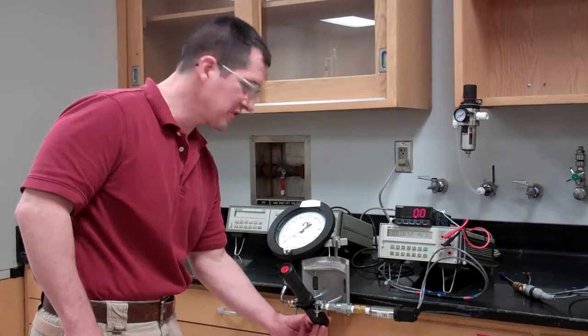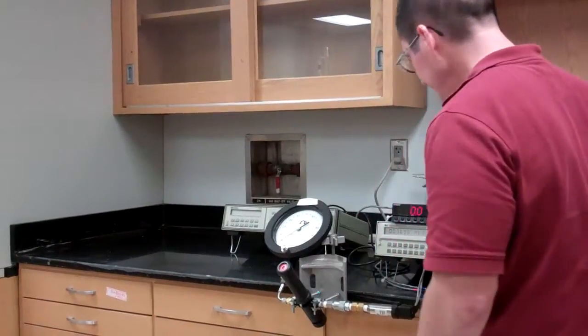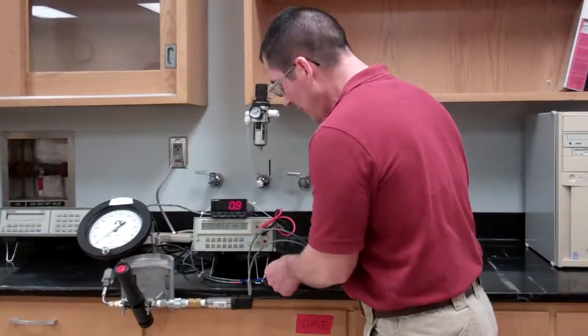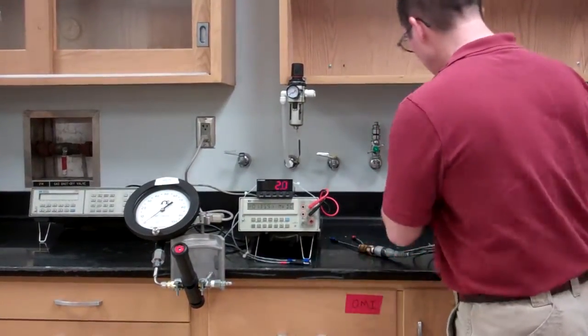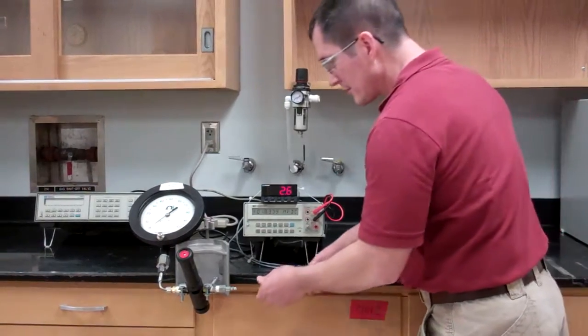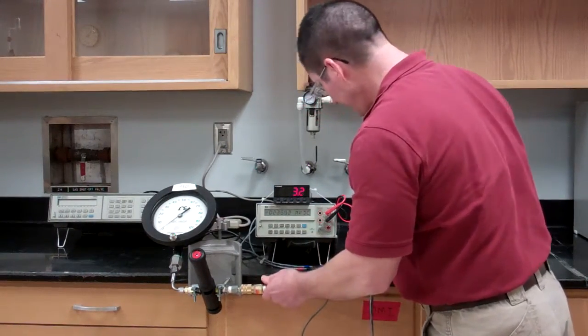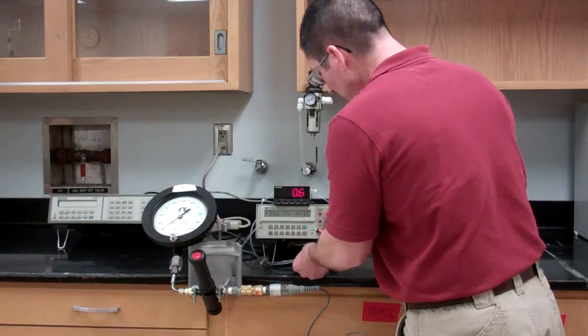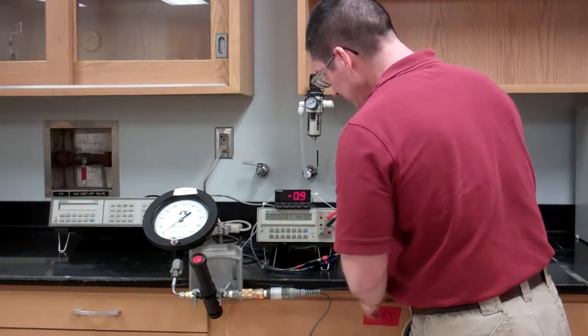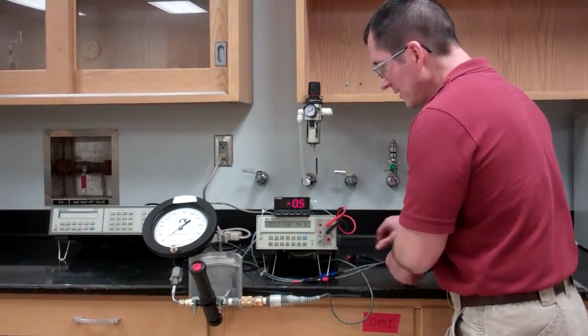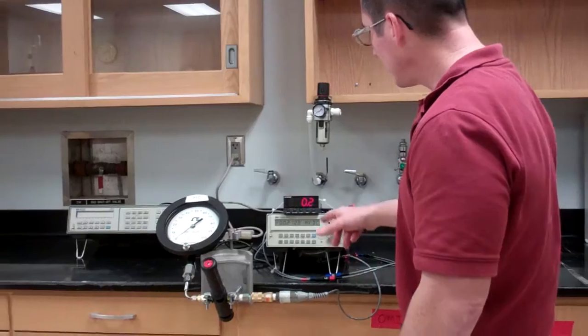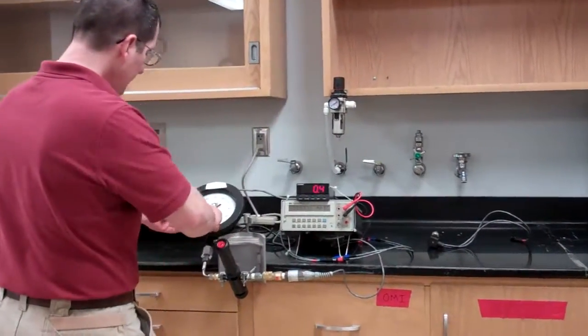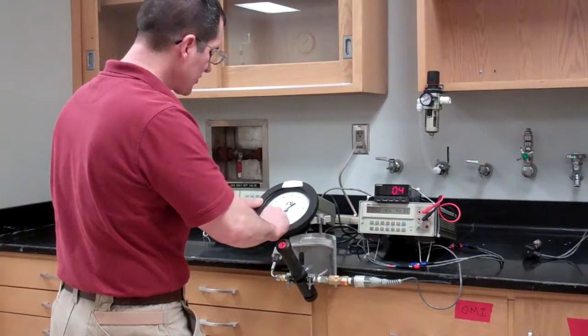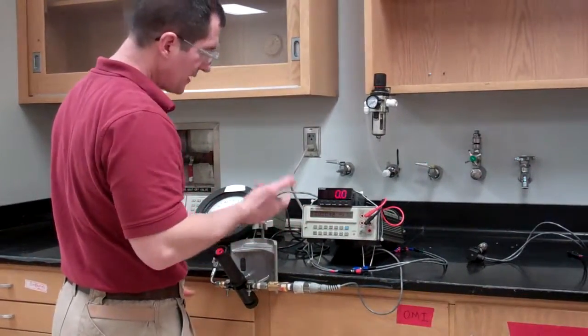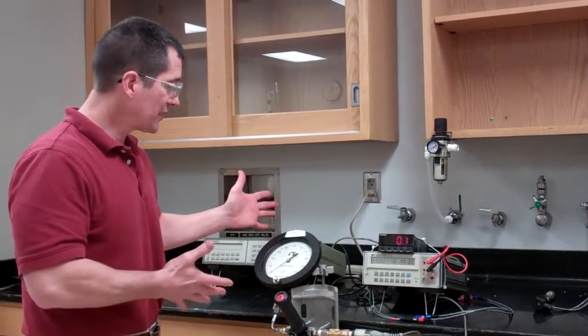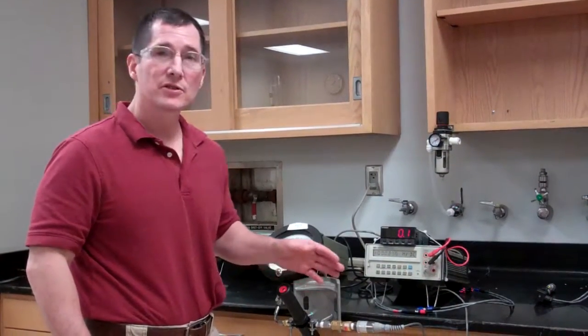So I'm just going to show you quickly how to change over from one transducer to the other. You can disconnect the power supply and the signal. Take this off, click disconnect. Plug that in. Blue, red. That's it. And if you need to, you can adjust the tare on here. So make sure this is zeroed out, and you press the tare button, and then you're ready to go. So this is 710, the pressure transducer calibration station.